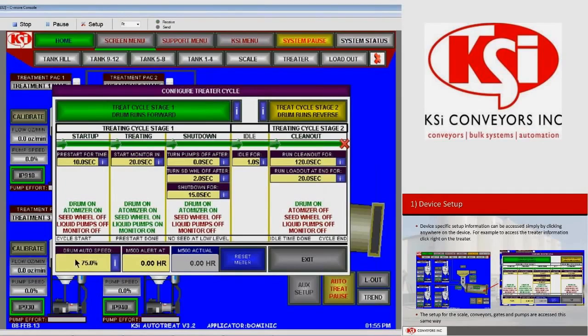Along the very bottom, we have a drum auto speed. This is how fast your drum is going to run when it is in auto, 75%. We like to see this usually not higher than 90%. And then we have an alert set for the drum motor, again, just to monitor the use of that motor. And then once we're done here, we can just exit out of this.